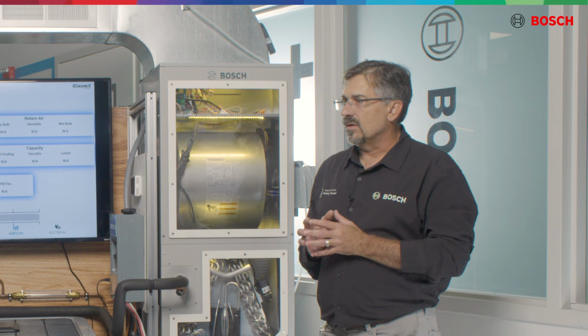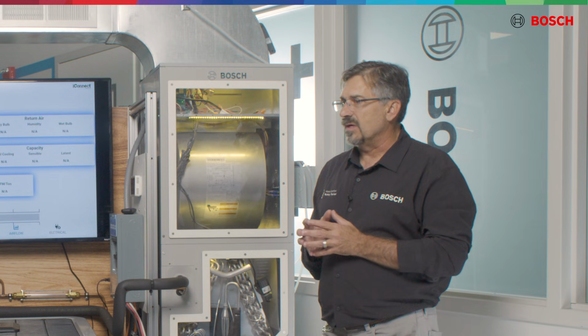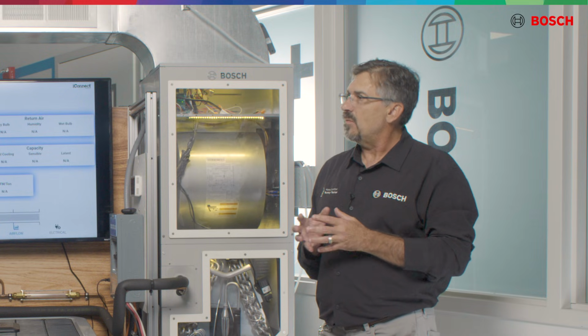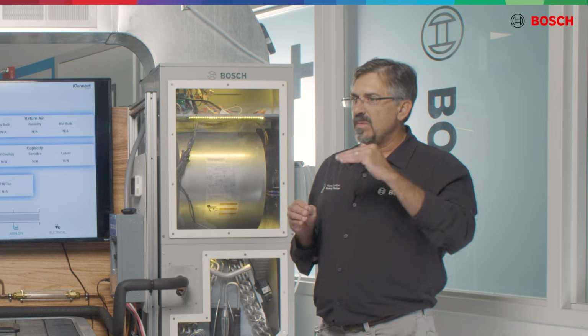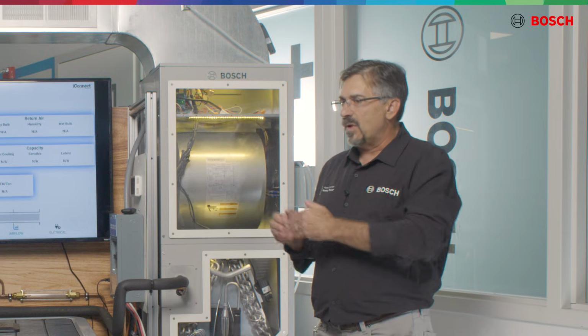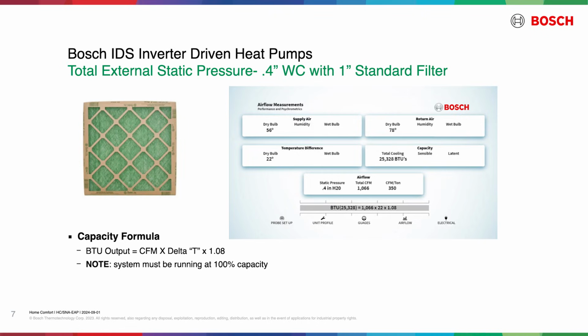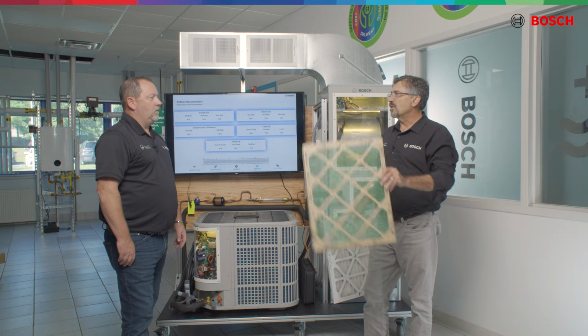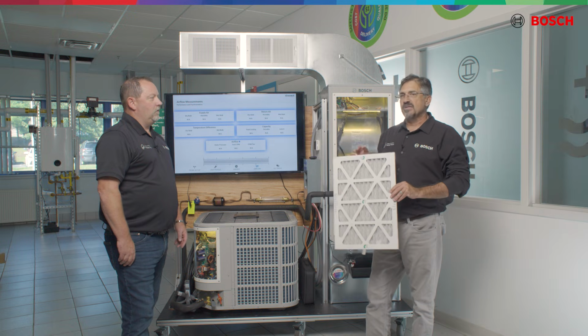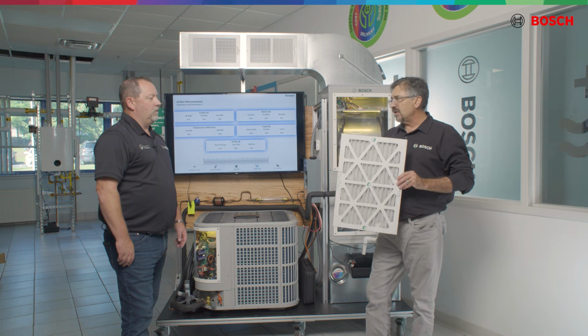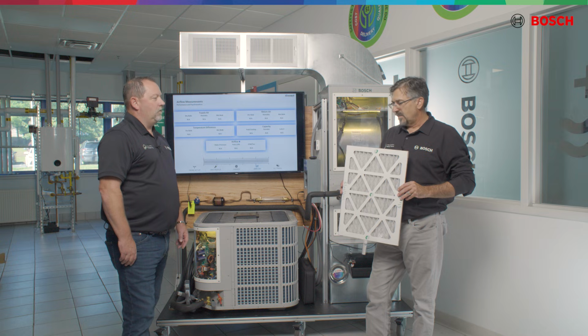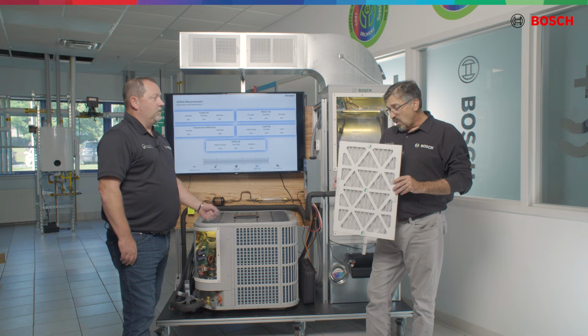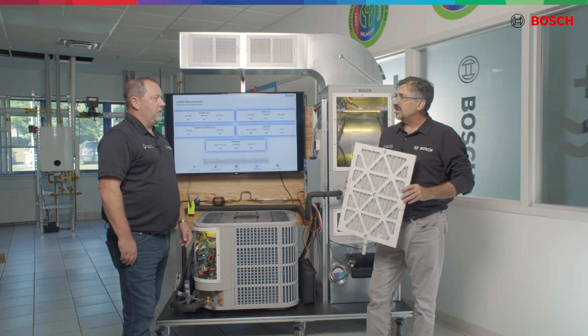So like I said, I alluded to the filters. We'll do our example here, but a 1-inch filter is really what we want. When we go to a media filter, 4-inch or 1-inch, right there alone is restriction on our air. At 0.4 static pressure, this blower motor was moving what we wanted, 1,050 CFM. The homeowner removed this filter and installed this filter. This is a pleated MERV 11 filter. A little bit more restrictive. It gets bigger particulates and dander.